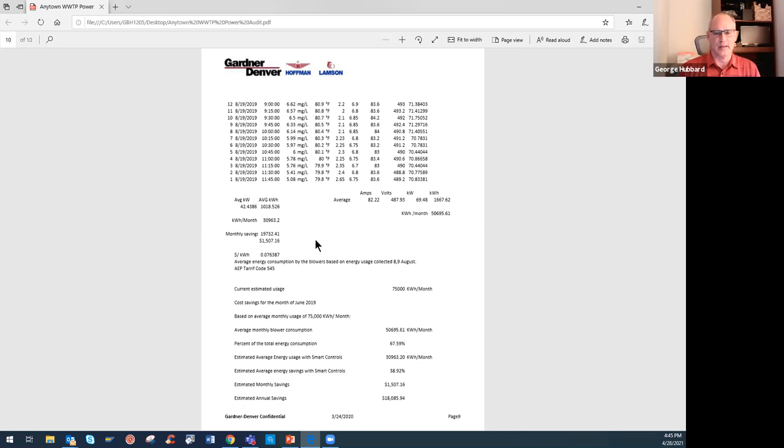But I specifically focused on multi-stage here because it is the older technology. Over the years, that was the accepted technology. And over the last 15 years, some of these more efficient blowers have come on, and some of the multi-stages have been replaced with those. So an energy audit might give you reason to pause and take a look at where your current system is operating. More importantly, where was it originally designed to run and where is it running now? So you may not have to put in a new technology.